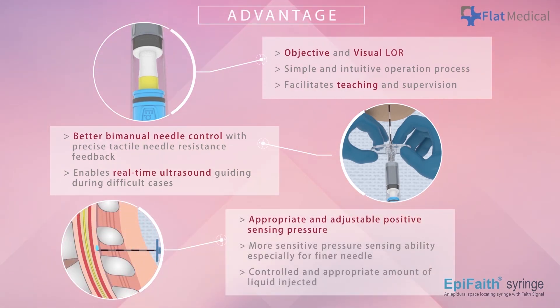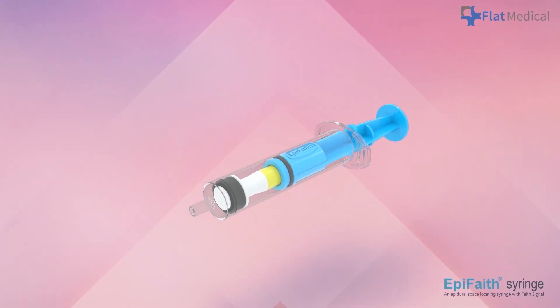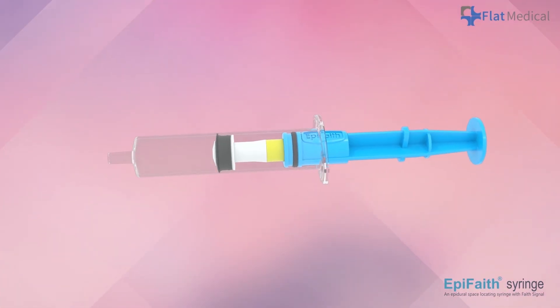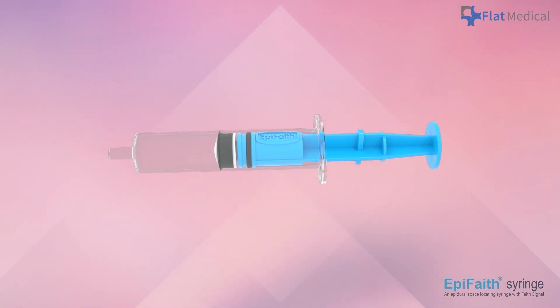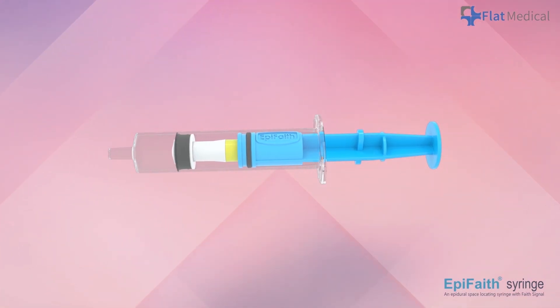Last but not least, the sensing pressure is well designed to remain safe even in elevated epidural pressure situations. Additionally, EpiFaith automatically injects an appropriate amount of fluid, gently expanding the epidural space to reduce the risk of over-puncture. EpiFaith syringe improves epidural localization with its user-friendly design, safety features, and the ability to simplify procedures while minimizing risks.